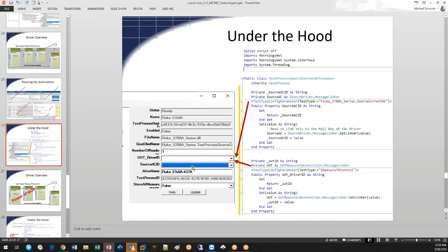So there may be a time when you want to use two 5700s together to calibrate something like a Yokogawa power analyzer, or you could run two voltmeter calibrations at the same time with those two 5700s configured inside of that workstation. And we can add to this. So this type equals definition in here with our attributes, we can put a comma and put multiple types in there. So we may have a generic process that will let us use a 5700 or a 5500. We can put both of those in there and allow several processes to be called. And that's what populates this dropdown.